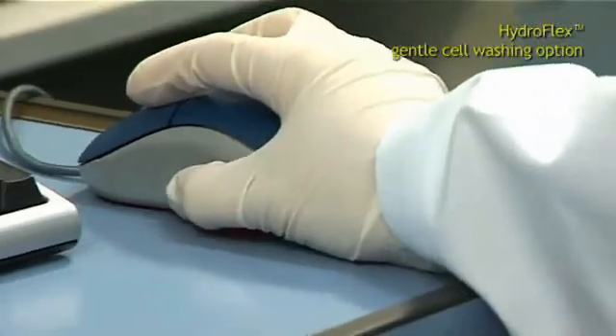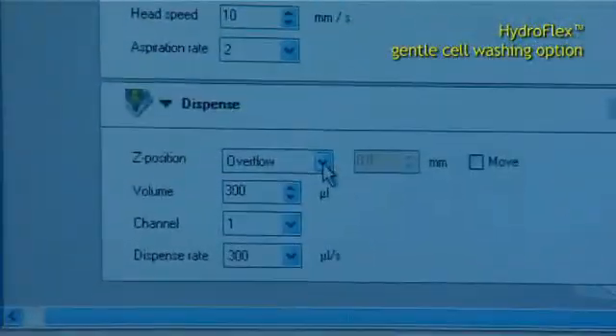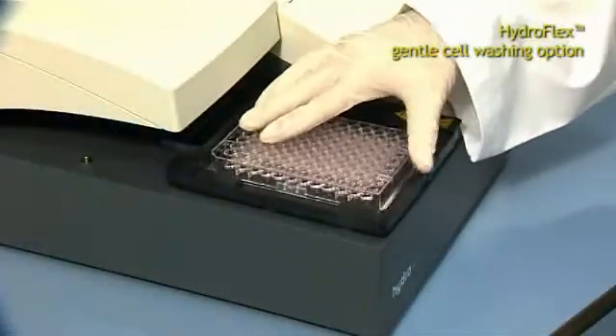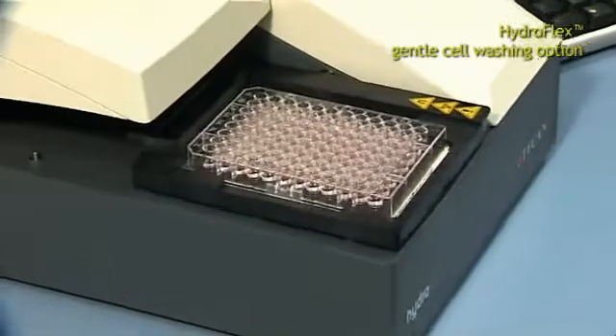Only three clicks of the mouse and an ELISA wash protocol can be adapted to a cell wash program. No hardware change is necessary. The same manifold can be used for either ELISA or cell washing.